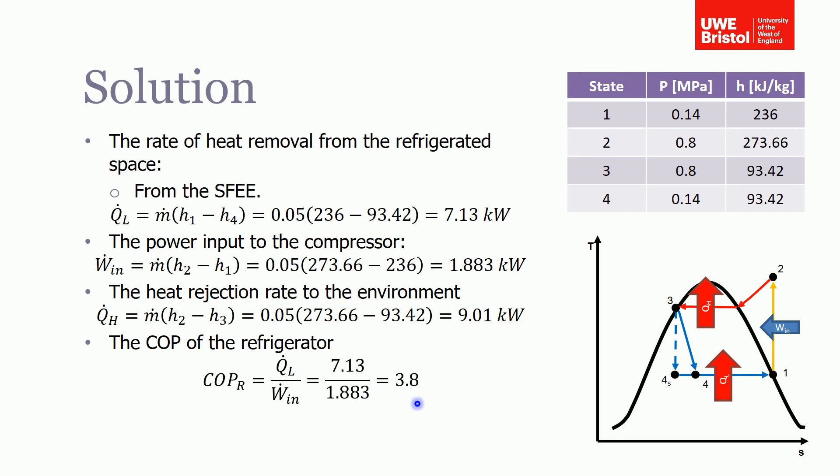If we put the two values in there and get that ratio, we end up with a coefficient of performance of 3.8. So in other words, for every one unit of electrical energy, it removes 3.8 units of energy from the refrigerated space.